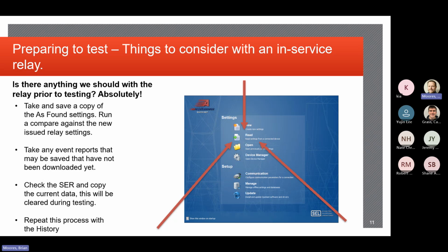But anyways, long story short, make sure you understand the nomenclature being used, whether it's read, write, send, open. I can't remember what GE uses; SEL uses read and send, I believe. Cooper obviously was upload, download, but it's important to understand that. And having that set of settings tucked away, you can use it for reference, and if you ever have to put it back in for an emergency purpose, you have a copy of it.